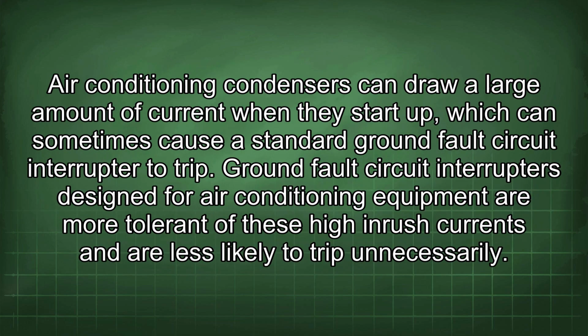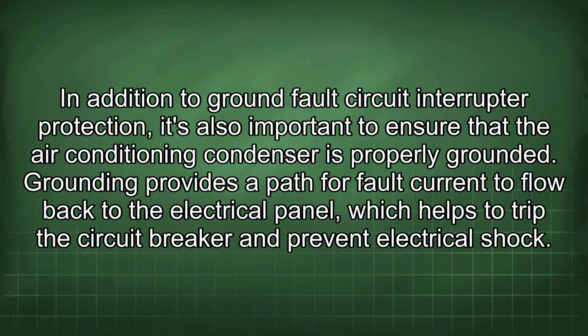Air conditioning condensers can draw a large amount of current when they start up, which can sometimes cause a standard ground fault circuit interrupter to trip. Ground fault circuit interrupters designed for air conditioning equipment are more tolerant of these high inrush currents and are less likely to trip unnecessarily.